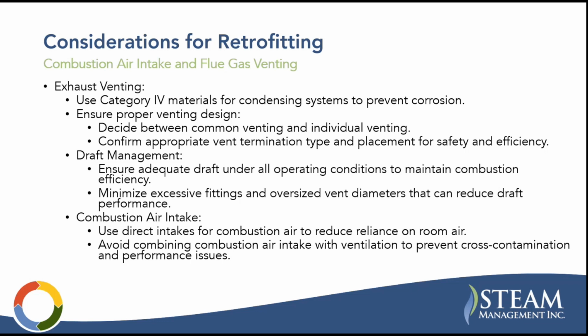You have to choose proper venting design. Are you going to do a common vent or an individual vent for each boiler? The individual vent makes it much simpler from an operational standpoint, but obviously then you're having more penetrations through your wall or roof for that vent line. And then you want to choose appropriate vent termination types. A vent with a rain cap is not recommended. You don't want to do anything to slow down the velocity coming out of that vent.